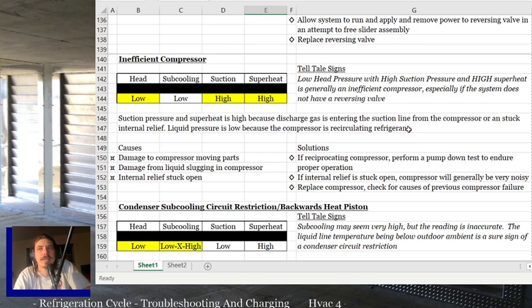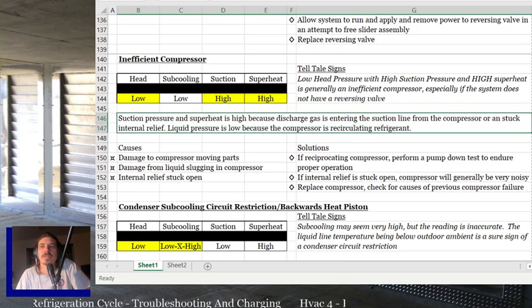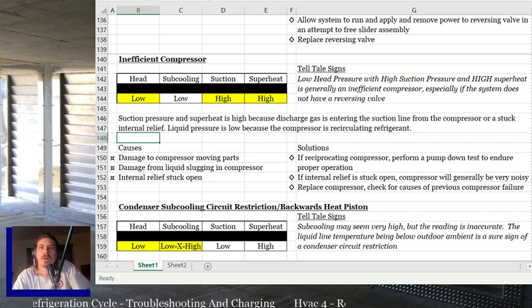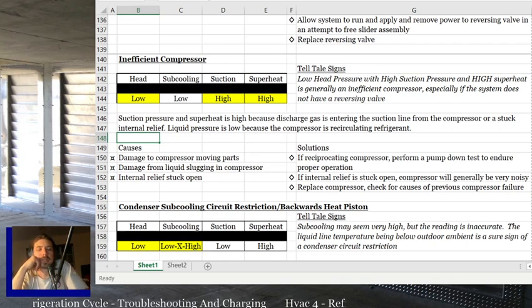Suction pressure and superheat are high because discharge gas is entering the suction line from the compressor or a stuck internal relief. Liquid pressure is low because the compressor is recirculating refrigerant. The cause is damage to the compressor's moving parts. Especially if it's reciprocating, you've got check valves, suction valves, piston rings, all kinds of stuff that seal up the parts in there. If they're damaged, it's going to pump gas back the wrong way here and there. Damage from liquid slugging in the compressor can cause damage to those internal parts.